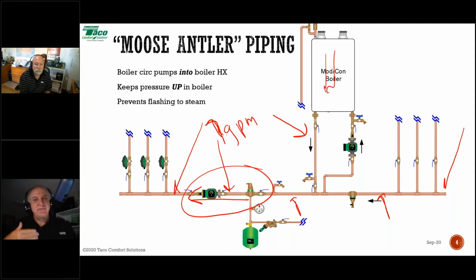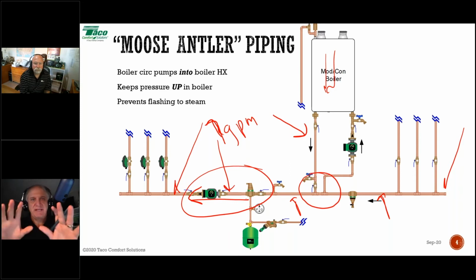In fact, there is a little bit of a benefit to oversizing the header. A shorter, fatter header gives better hydraulic separation at that point right there, where the boiler loop connects to the delivery loop. So there is an advantage to oversizing that header. So in this example, it should be at least 1 inch. 1.25 inches is not going to hurt you any. In fact, it could help a little bit. But that's piping up with just a field fabricated header.